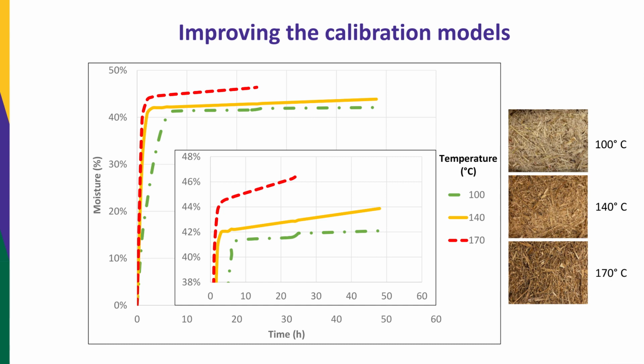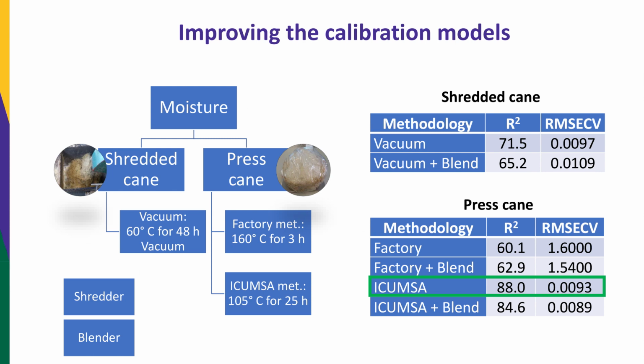When you are burning your sample, you are just releasing organic acids, you are releasing other components, and when that happens, you are accounting that as moisture, and it's not. So that's why the moisture of those two temperatures is higher than the moisture at 100. So now I decide to move forward and use this methodology at 105 because that's the temperature that ICUMSA recommends for this kind of samples.